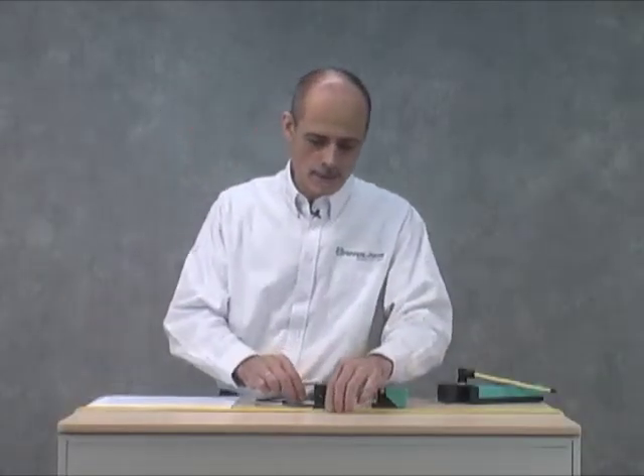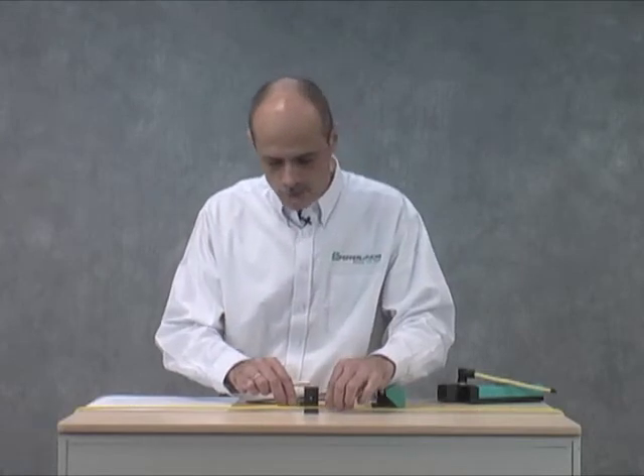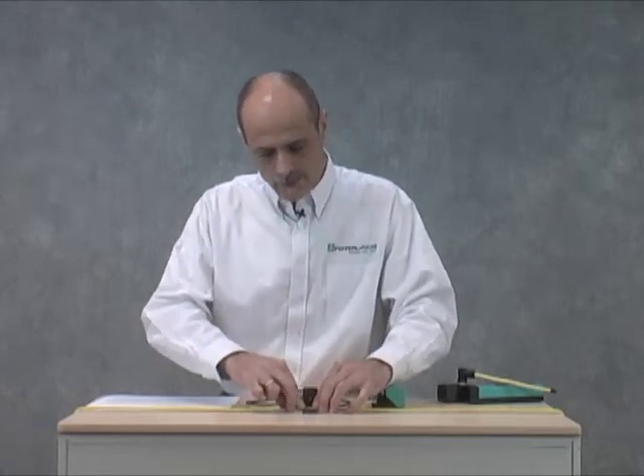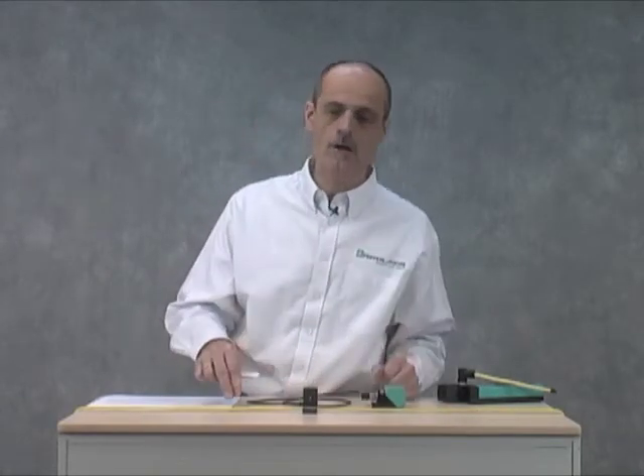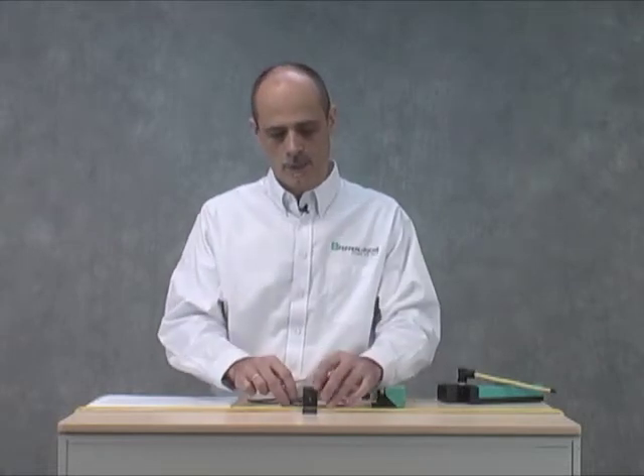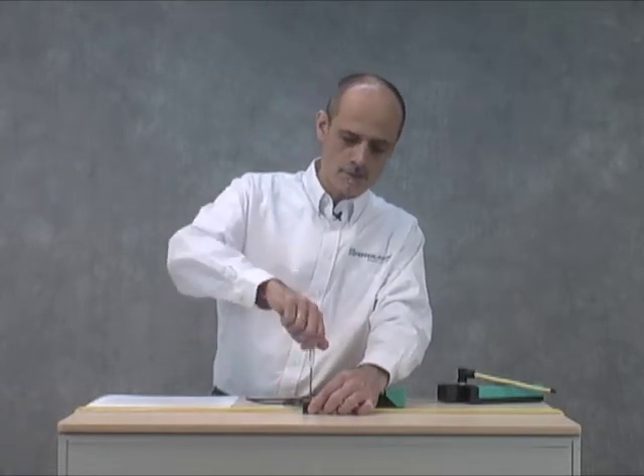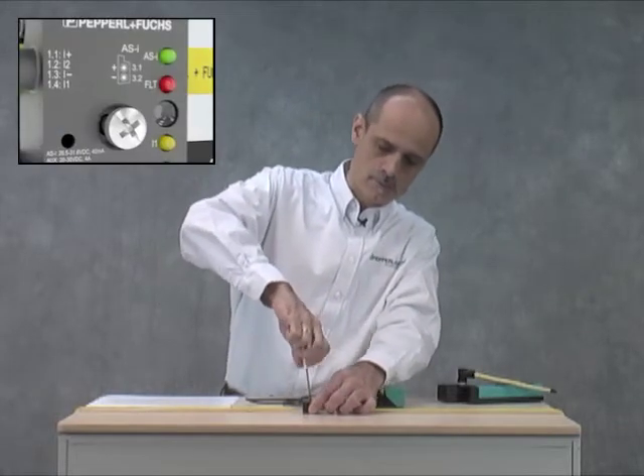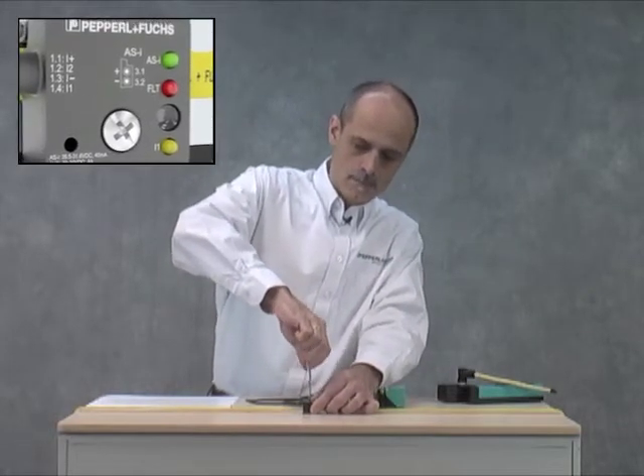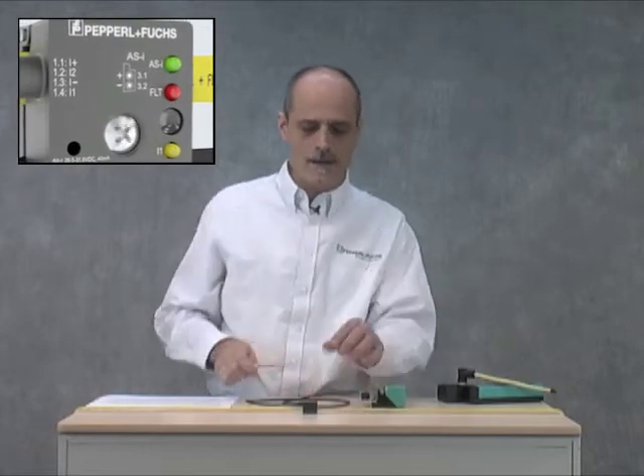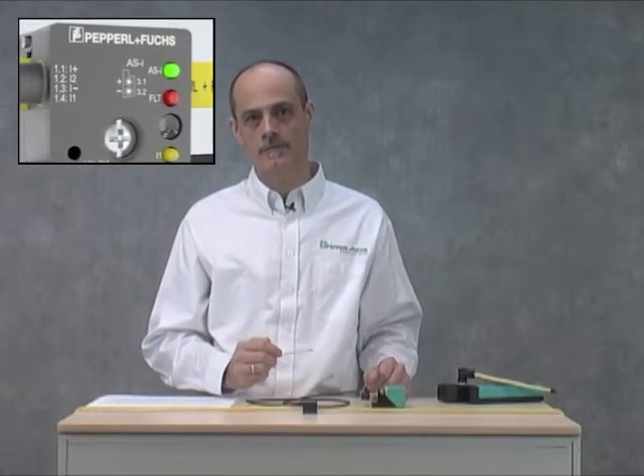After addressing the module, insert the yellow AS-interface network cable, and if present, the black AUX power cable. Then close the module and secure the stainless steel center screw. Because I did this onto a live network, the module immediately goes active.